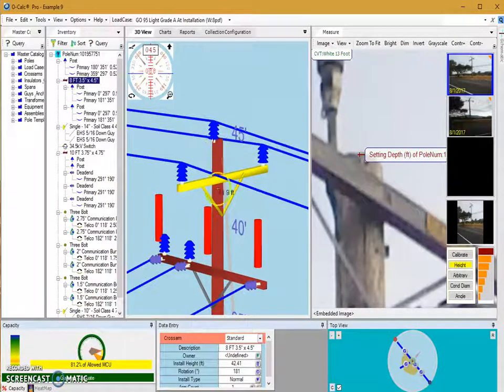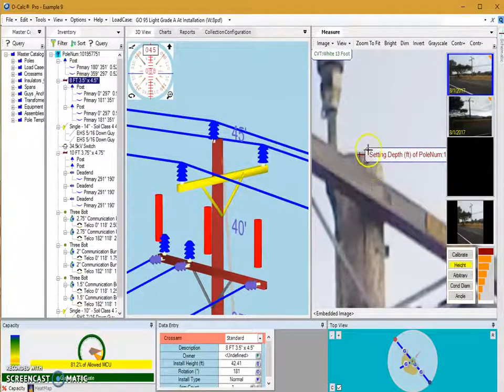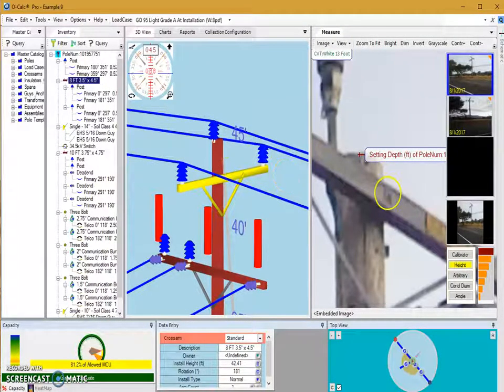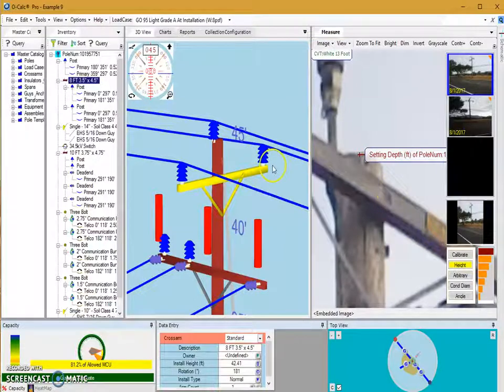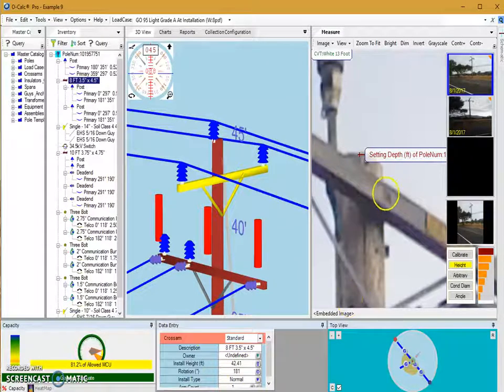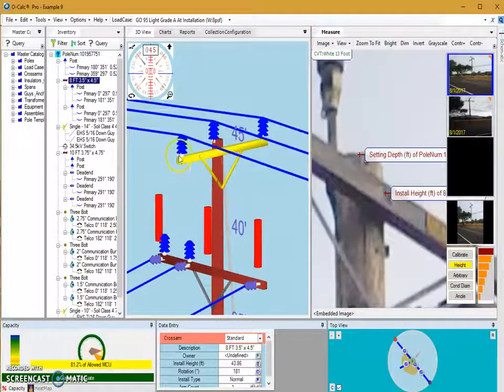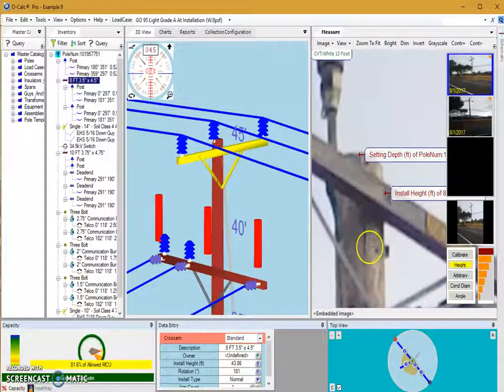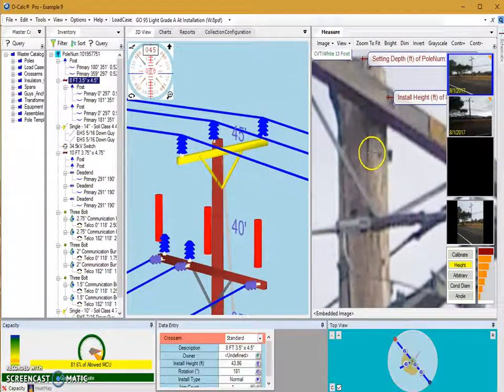I'm selecting this top cross arm and want to change its attachment height. In our 3D view there's quite a bit of space between the tip of the pole and that cross arm, whereas in our image there's not a whole lot. You use the through bolt visible in the image — that's where our attachment height is going to be. With the cross arm selected, I click where that through bolt is to change the height, and you'll see it moves up accordingly. Capacity utilization did not change very much.